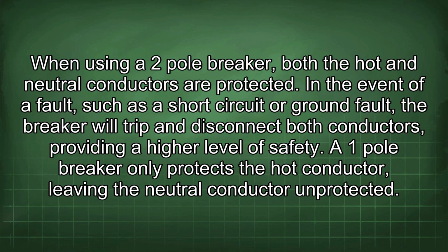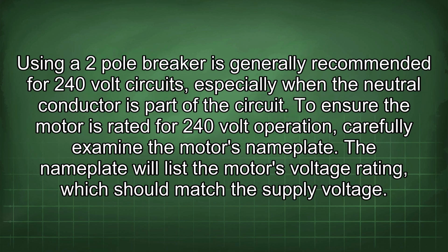When using a two-pole breaker, both the hot and neutral conductors are protected. In the event of a fault, such as a short circuit or ground fault, the breaker will trip and disconnect both conductors, providing a high level of safety. A one-pole breaker only protects the hot conductor, leaving the neutral conductor unprotected. Using a two-pole breaker is generally recommended for 240-volt circuits, especially when the neutral conductor is part of the circuit.